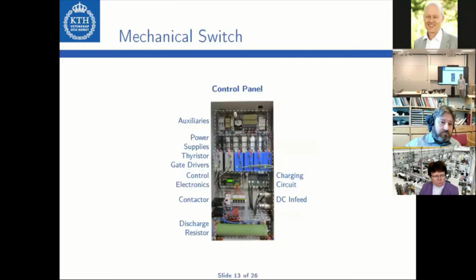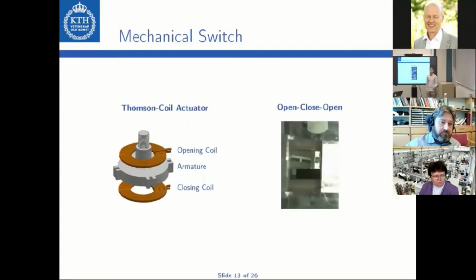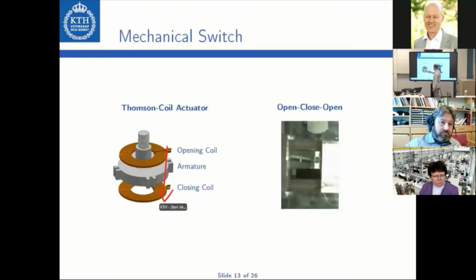Here you can see the inside of the control panel. It houses various electronic components needed to control the actuator and to energize its coils. On the left-hand side, you can see an illustration of the Thomson coil actuator. It has two coils, an opening coil and a closing coil, and a metallic armature between them. If the opening coil is energized, the armature is pushed towards the closing coil. For a closing operation, the procedure is the other way around.